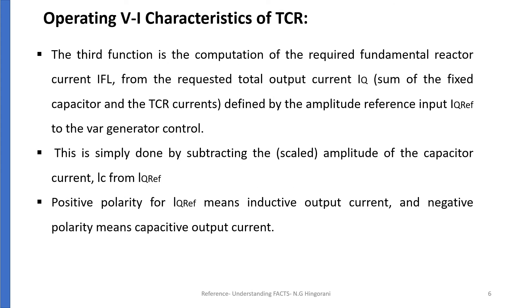The third function concerns the operating VI characteristics of TCR — the computation of required fundamental reactor current from the requested total output current Iq, defined by the amplitude reference input Iq_ref to the VAR generator control. This is done by subtracting the amplitude of the capacitor current IC from Iq reference. Positive polarity of Iq reference means inductive output current; negative polarity means capacitive output current.